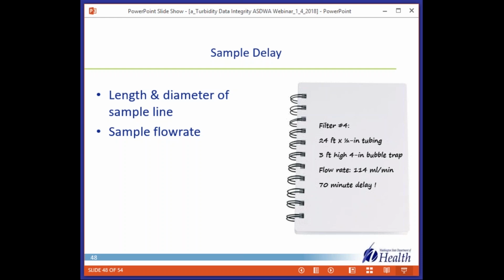So if they had a critical alarm attached to that, you can imagine by the time the alarm went off, the water would already have been 1 hour away. So here's a tip. Use short, small diameter sample lines. Aim for a sample delay of no more than a minute if you can. You want the smallest tubing that can deliver the flow you need, and high velocities will help keep biofilm from accumulating in those lines.